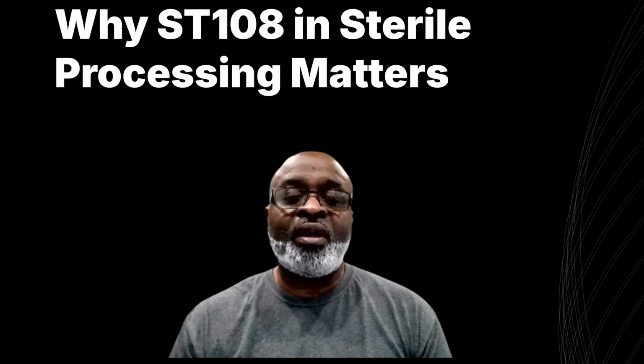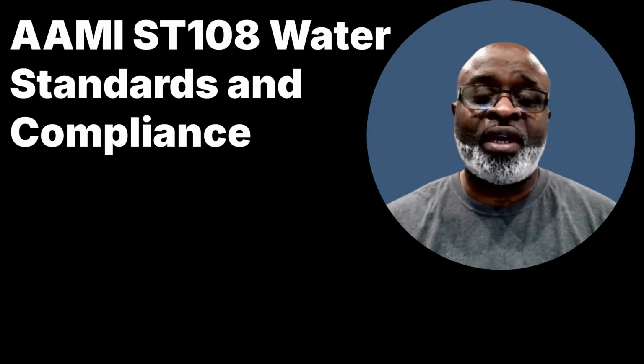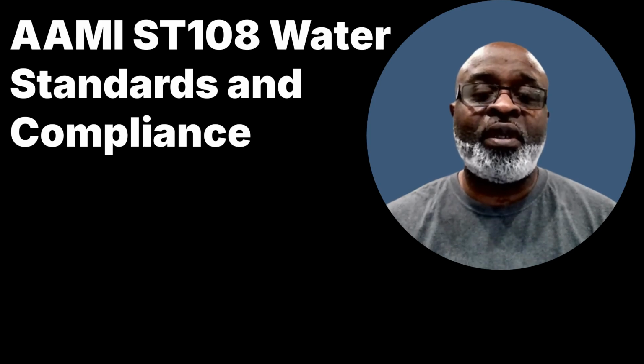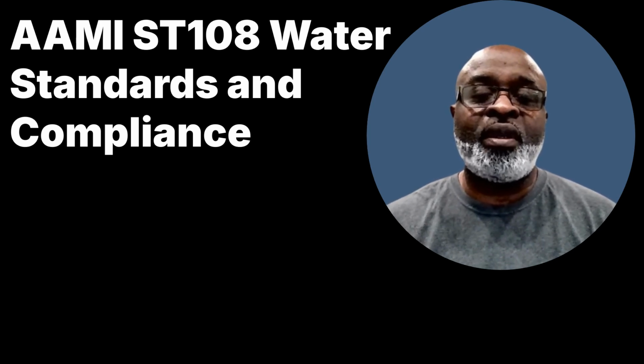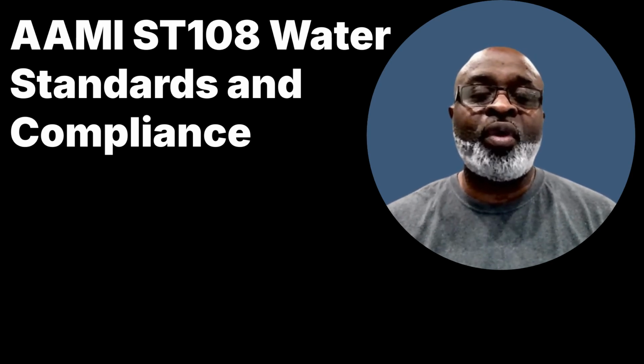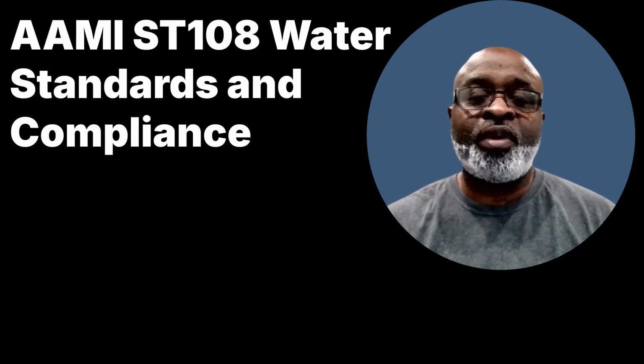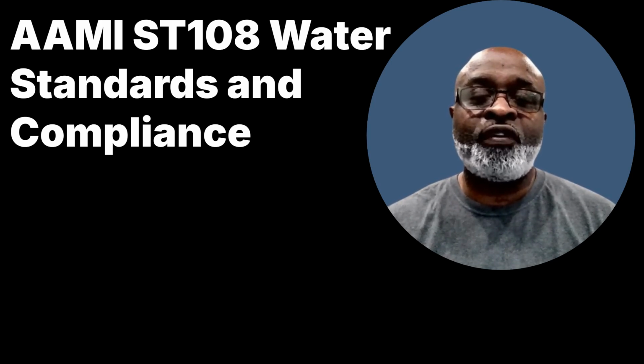Poor water quality can cause damage, biofilm, and ineffective cleaning. The AAMI ST108 sets utility water, critical water, and steam standards. Utility water is used for basic cleaning. Critical water requires advanced purification, and steam must be impurities-free to ensure safety and effectiveness. To comply, we have assessed our water system to determine treatment requirements. We are creating a plan to maintain compliant sterilization water quality, establish regular check frequencies, and ensure ongoing compliance and safety.